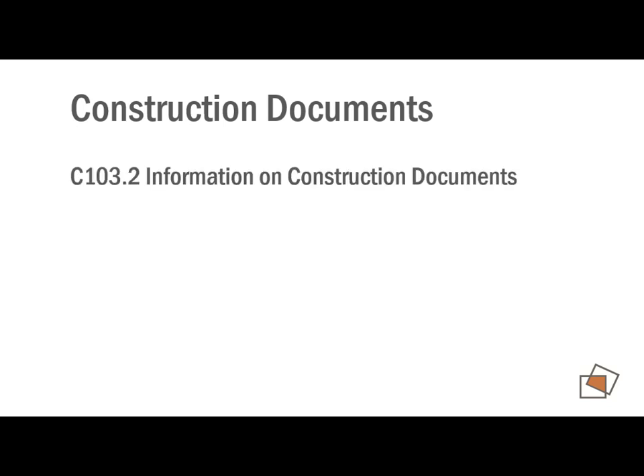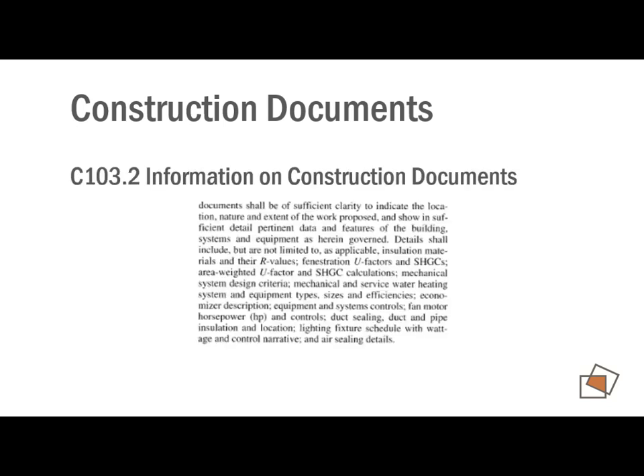But let's talk about what to put on your construction documents that shows you're complying with this. It's got this section in here, C103.2, which lists all these things that the construction documents are supposed to include: U factors, solar heat gain coefficients, R values, equipment efficiencies, sizes. A lot of that stuff's probably on there already because we're specifying it.